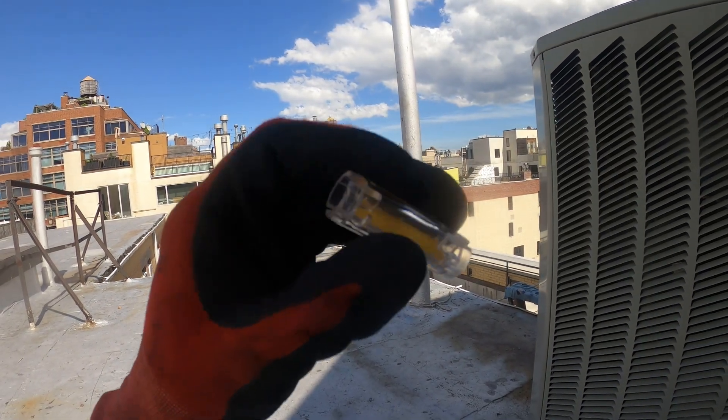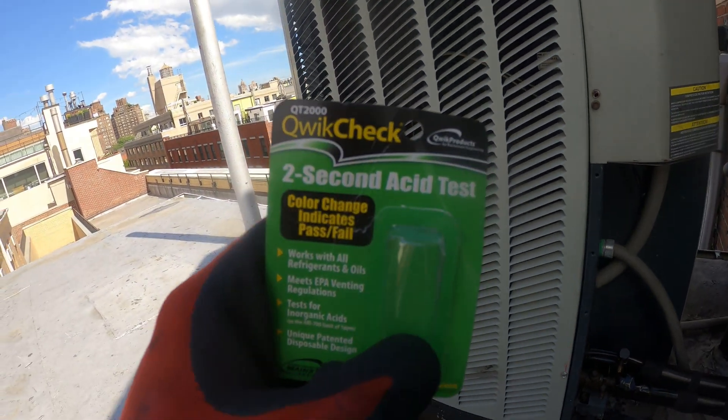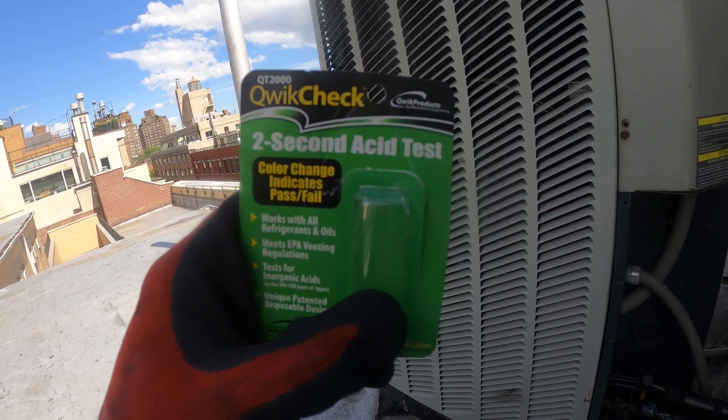I did not see a color change, so this checks out for not having acid. And that was the QwikCheck two-second acid test.